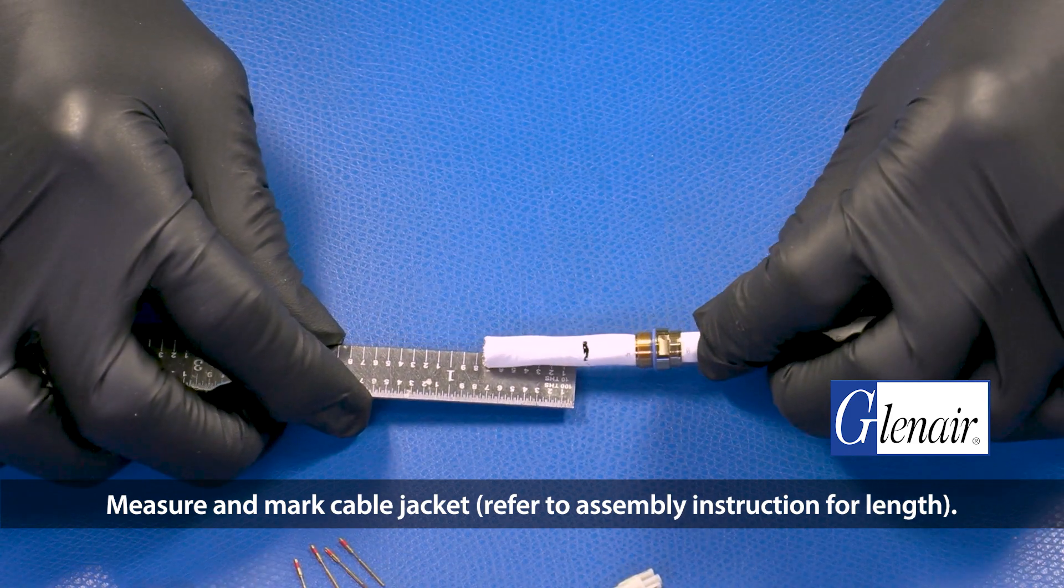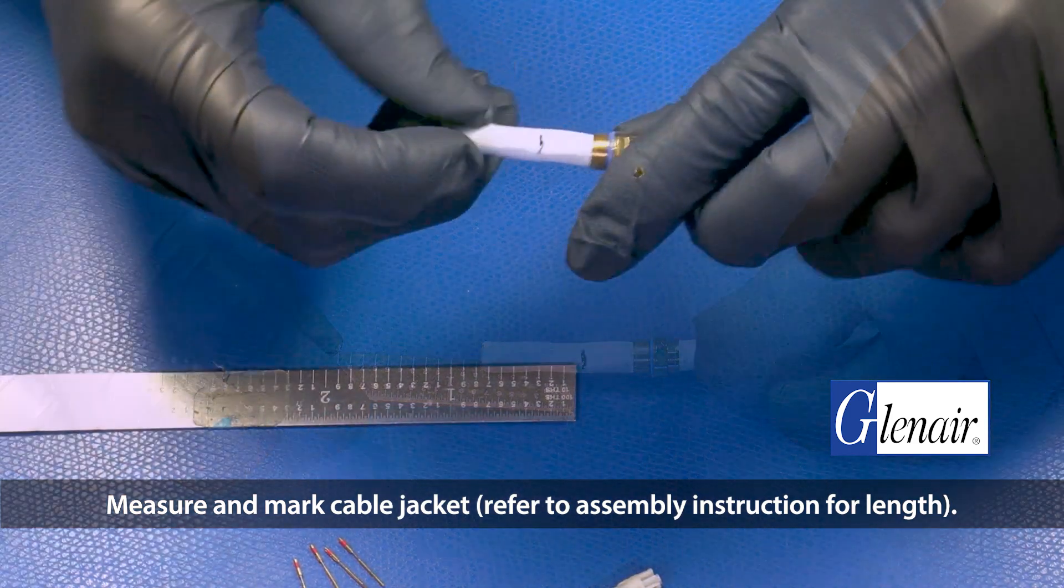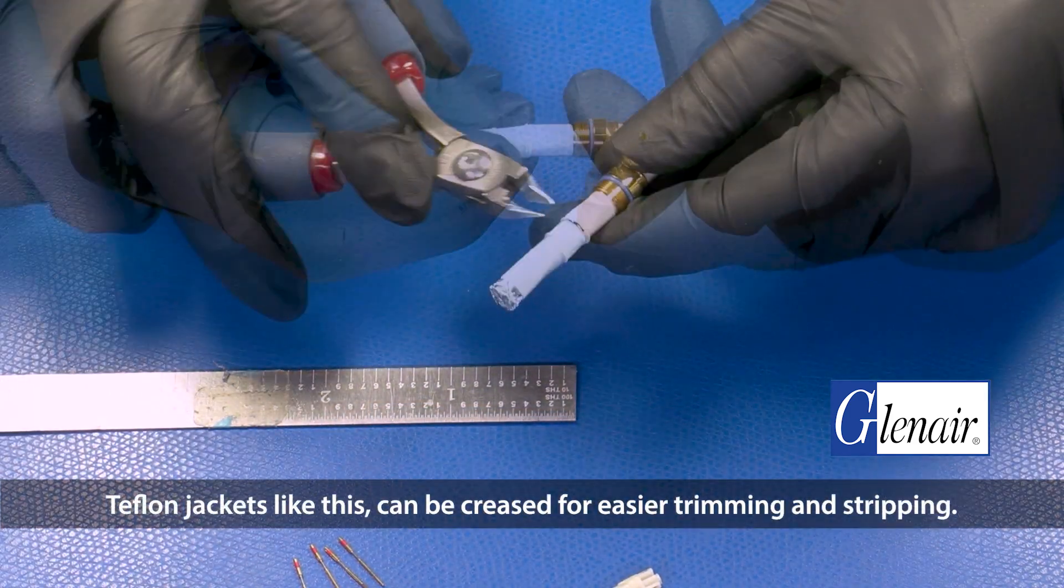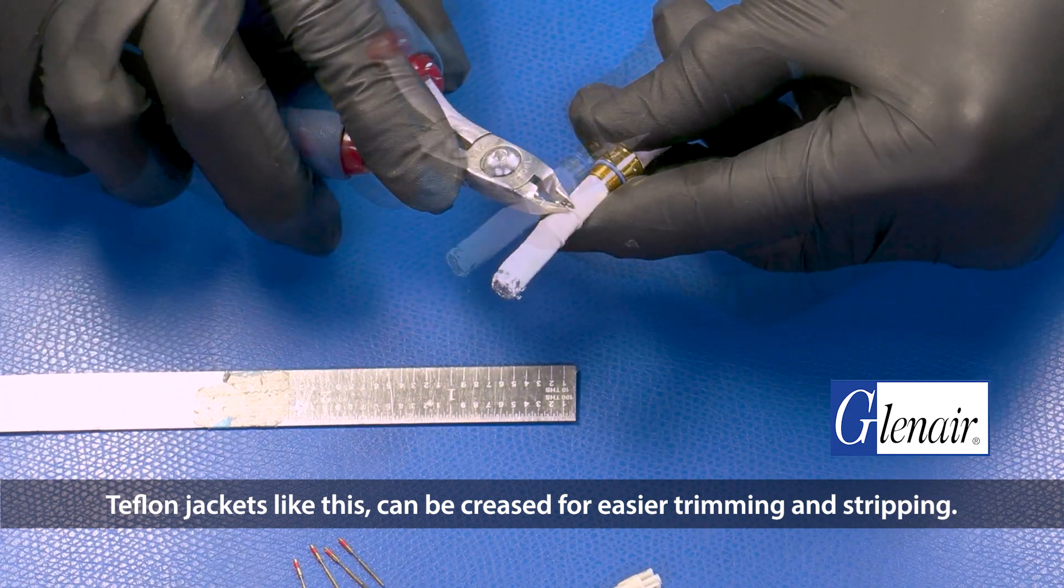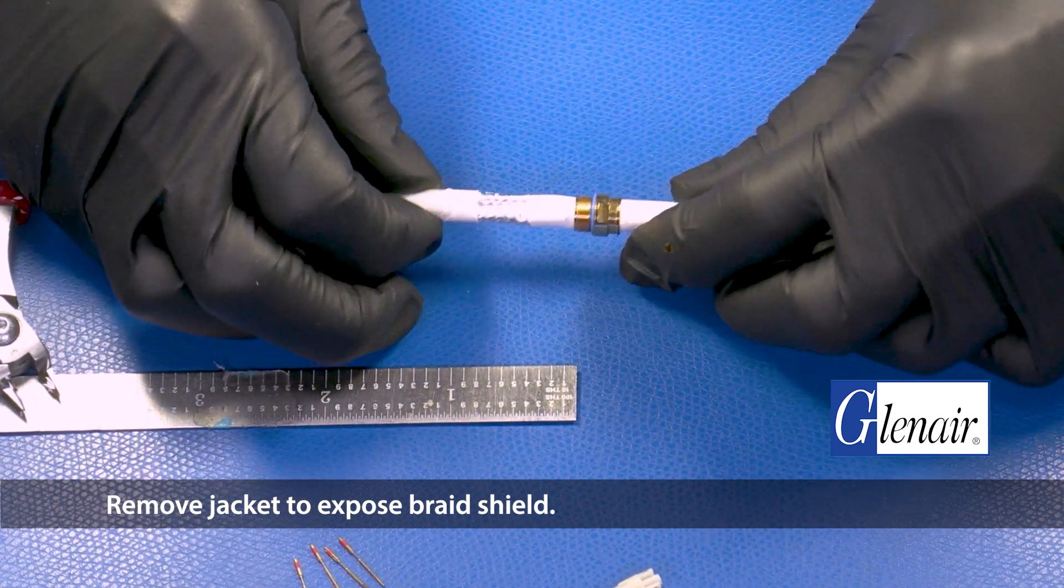Measure and mark cable jacket. Refer to assembly instruction for length. Teflon jackets like this can be creased for easier trimming and stripping. Remove jacket to expose braid shield.